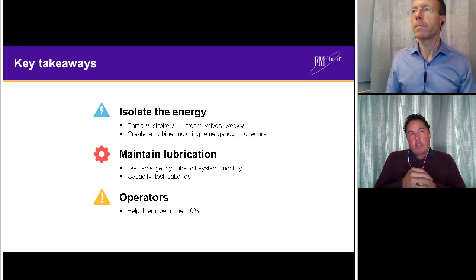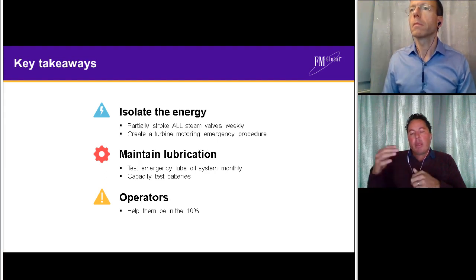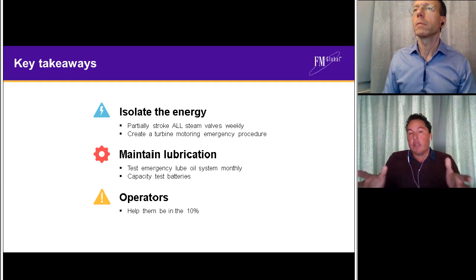Yes, is the short answer, Richard. It depends on a number of different factors. So we have some level of flexibility in what we recommend to our clients, depending on the risks that we find on site. So, for instance, if you look at steam valve testing, where ordinarily we would be looking at a weekly frequency for partial stroke testing on emergency stop valves and on bled steam non-returns, we envisage being able to stretch that to a four-weekly schedule if everything else is absolutely ship-shape and there are no other risks on that machine.